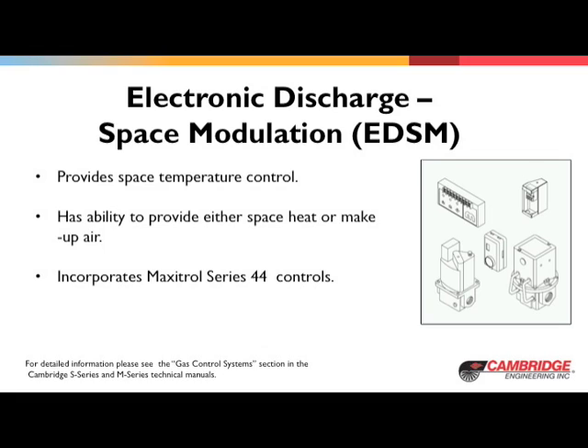EDSM incorporates Maxitrol 44 series controls. The components utilized are an A1044 amplifier, a TS144 discharge temperature sensor, a T244A space temperature selector, and either an MR212, an M511, or an M611 modulating valve.